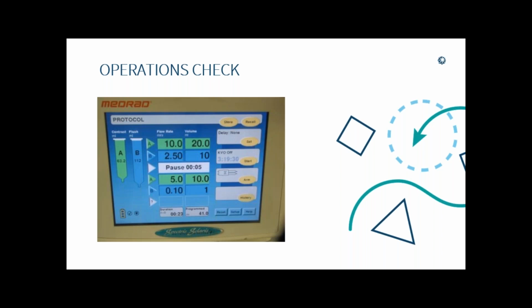You have your A side, B side, a pause, A side, B side, and you run that injection. What it does, you see a high speed flow, low speed flow, a pause, make sure that works. Then you have a medium rate flow, and then you have a very slow flow rate. So it tests all the parameters. And if you don't have a protocol to use on other injectors, you can use the same type of protocol: fast, slow, medium, very slow, medium slow, different volumes. You're checking out the whole system.